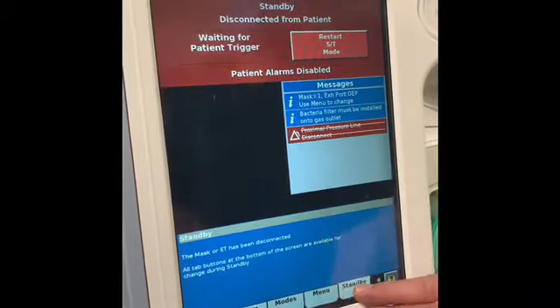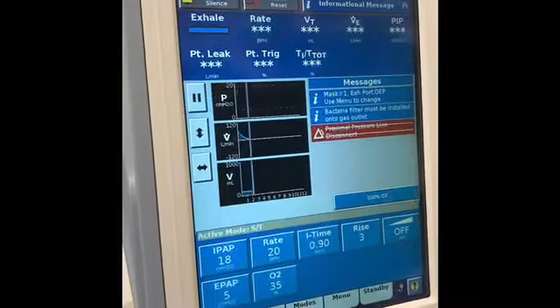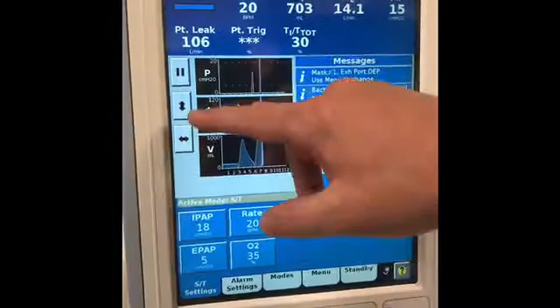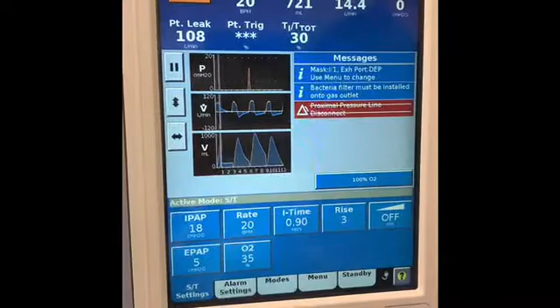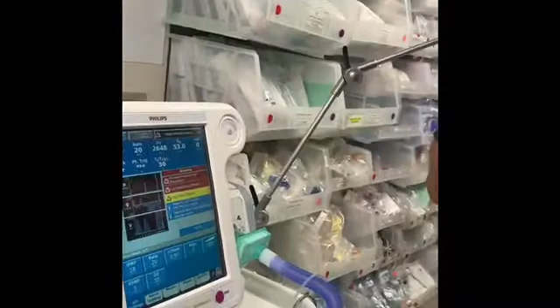All right, so there's two ways to do this. If you put the patient on a mask, they can actually trigger it, or you can just hit restart to ST mode. So now this is what you want to see. You want to see a blue screen. You want to see your tidal volume. You want to see your liters per minute. You want to see your pressure. Of course, this is ST, which means spontaneous and timed, so that it's patient initiated. So that's why it's going to alarm. If I were on this machine, it wouldn't alarm.